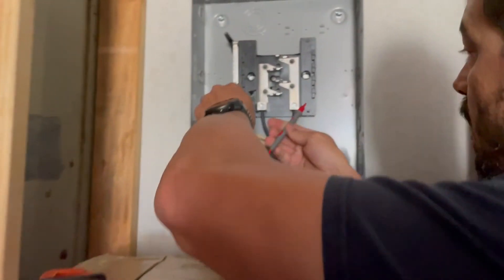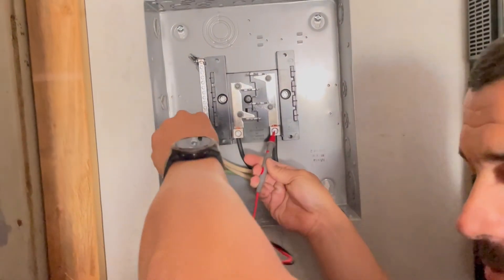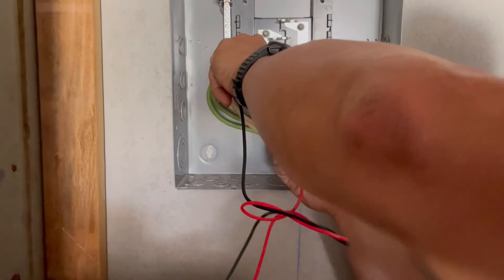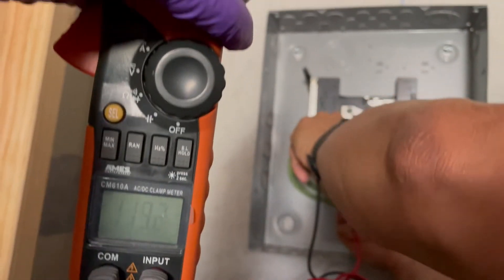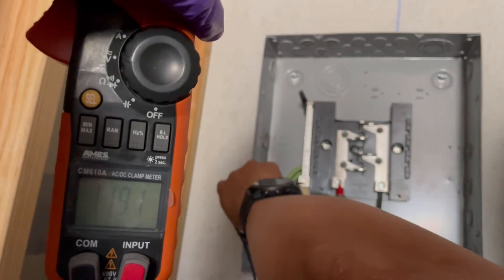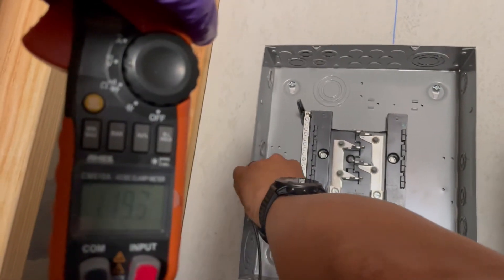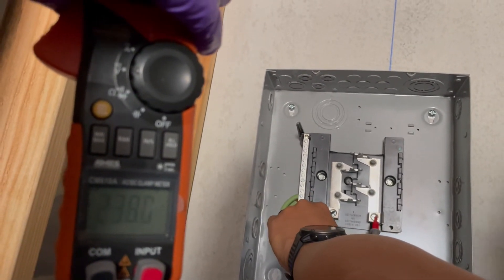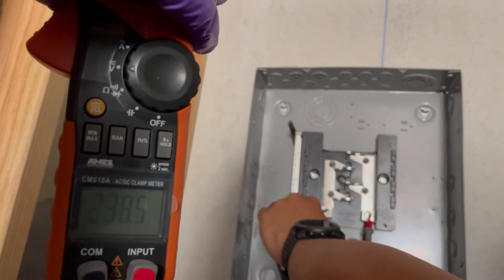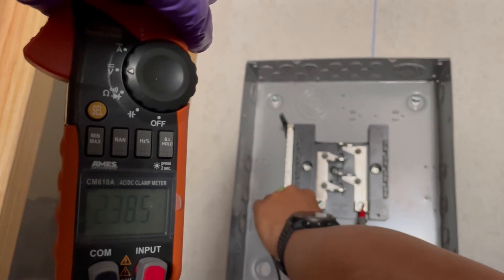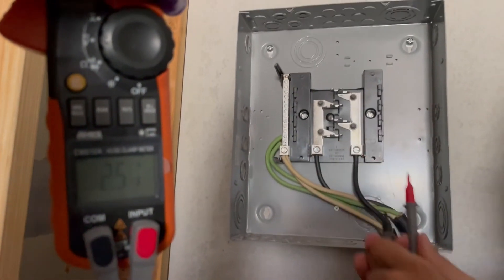So right now if I test this one to this one I should have 120 and I have 119. Let me see, so then over here I should have 119 as well. And then if I touch these I should have somewhere close to 240. 238! Oh yeah, that's what it's supposed to be.